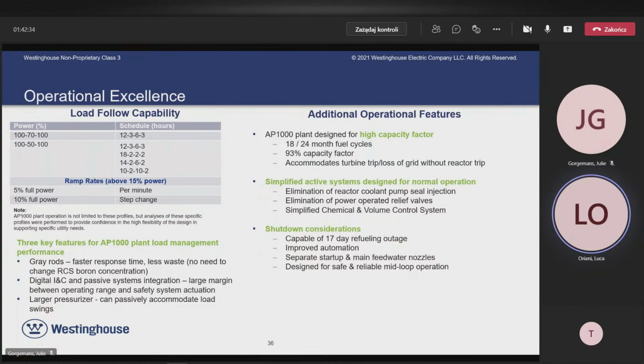Instead of only controlling power by changing the boron concentration in the water, which is slow and requires time, we change the reactor's power level by moving a specific set of control rods in and out of the core to modulate its power.